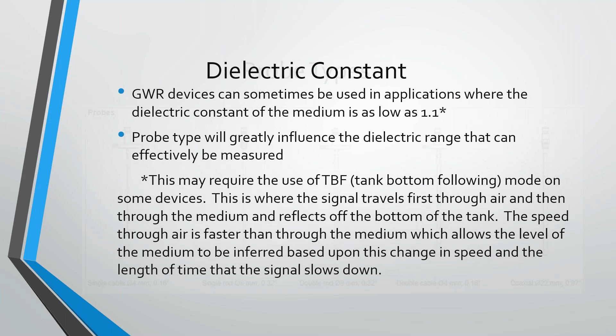But what happens is, even though we're not getting enough reflection from the material itself, the speed of the signal slows down as it travels through the medium. So the device is intelligent enough to measure the amount of time it took for the signal to travel at the higher speed through air, and then the amount of time that it was able to travel through the medium at a slowed down rate. And by taking a look at both of those values and doing some math, it's able to give us our level within the vessel, even though we're not getting a whole lot of reflectivity from the material itself.